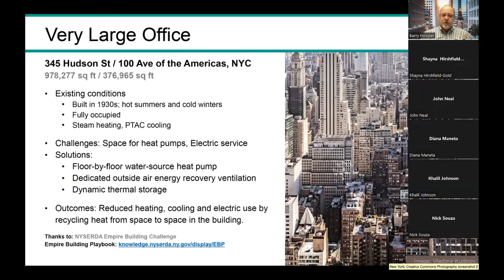They had a similar issue of space constraints and electric service constraints, and the solution took advantage of those existing conditions, using water source heat pumps as well as dedicated outside air with energy recovery to move heat around the building opportunistically. This is a more common solution in Scandinavia, but it's less about a heat pump pulling heat from outdoor air, and more about moving heat from one part of the building to another, with specifics varying seasonally.